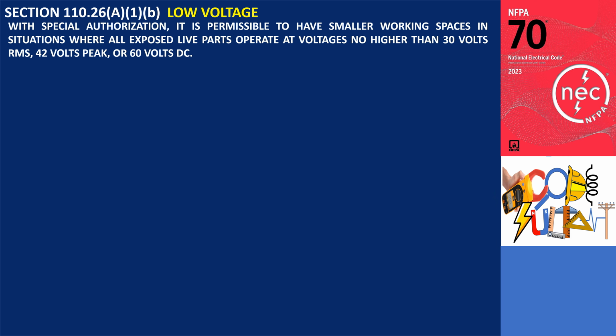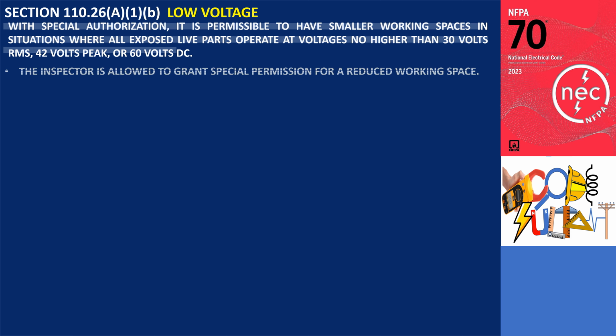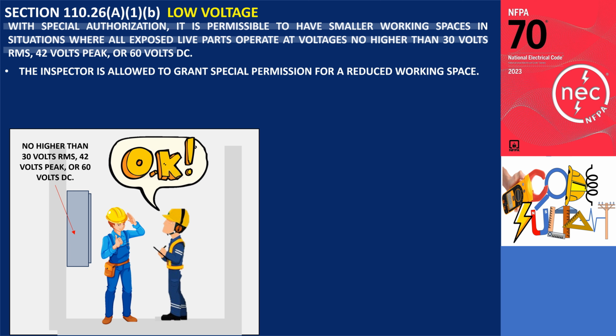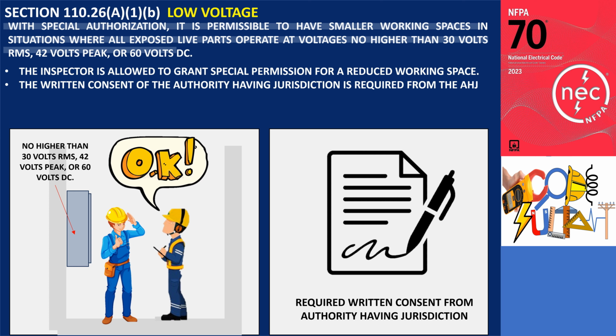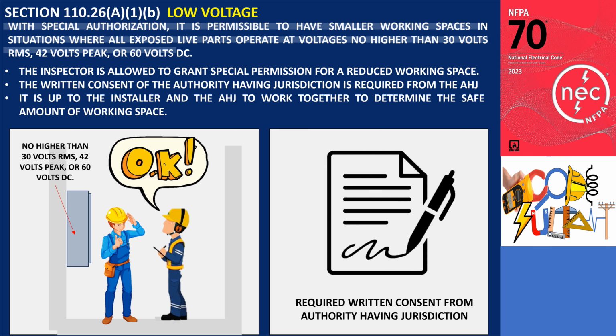Certain low-voltage installations also require less working space. If all the exposed live parts operate at not greater than 30 volts RMS, 42 volts peak, or 60 volts DC, then the inspector is allowed to grant special permission for a reduced working space. The definition of special permission in the NEC is the written consent of the authority having jurisdiction, so be sure to get it in writing. The specific amount of working space for these installations is not indicated, so it is up to the installer and the AHJ to work together to determine the safe amount of working space.